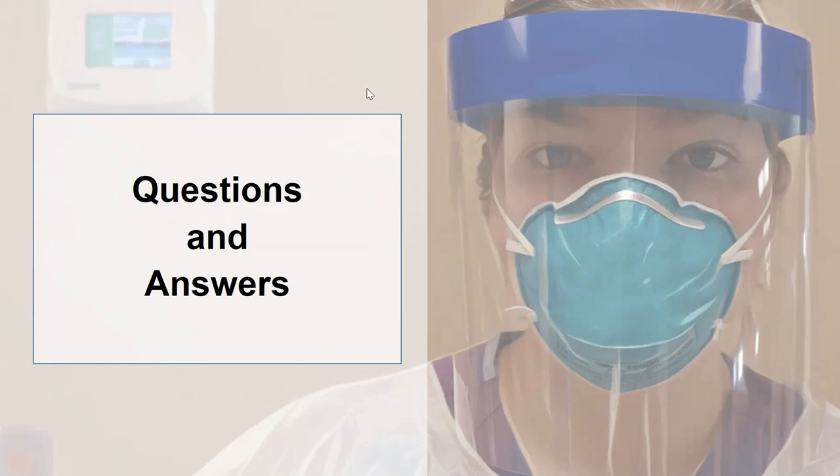Eric added: Nebraska Medicine chose to handle OR negativity with equipment within the OR. This question has been all over the national ASHE message boards. One thing to take into account is that the most appropriate way is to create a vestibule outside or, if you have enough room, immediately inside — so you can keep the operating room positive with respect to everything else, and then that vestibule collects the air and gets rid of it. This is referred to in the code as a combo room. Michael confirmed that's exactly how they did it at Bellevue — you walk into a neutral area that was negative to the corridor and the OR suite, where you could don PPE and scrub, then go into the OR which was more positive to the ante room than to the corridor.